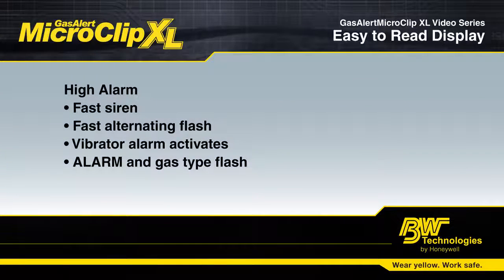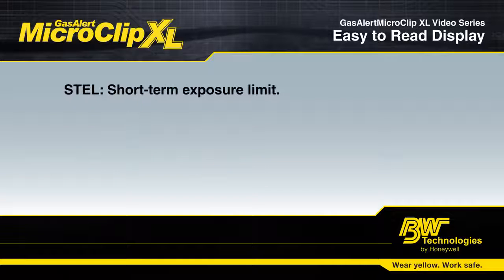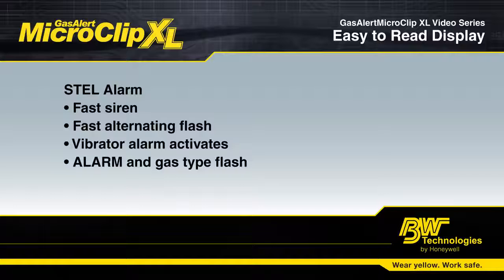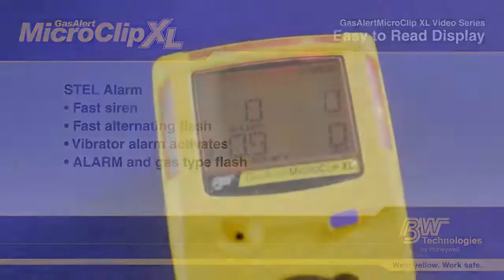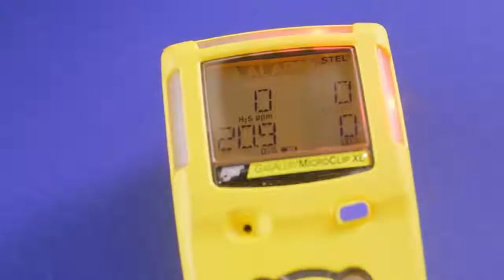STEL readings are calculated only for toxic gases. STEL stands for Short Term Exposure Limit, basically measuring your average exposure over a preset time period. This floating window can be set from 5 to 15 minutes.